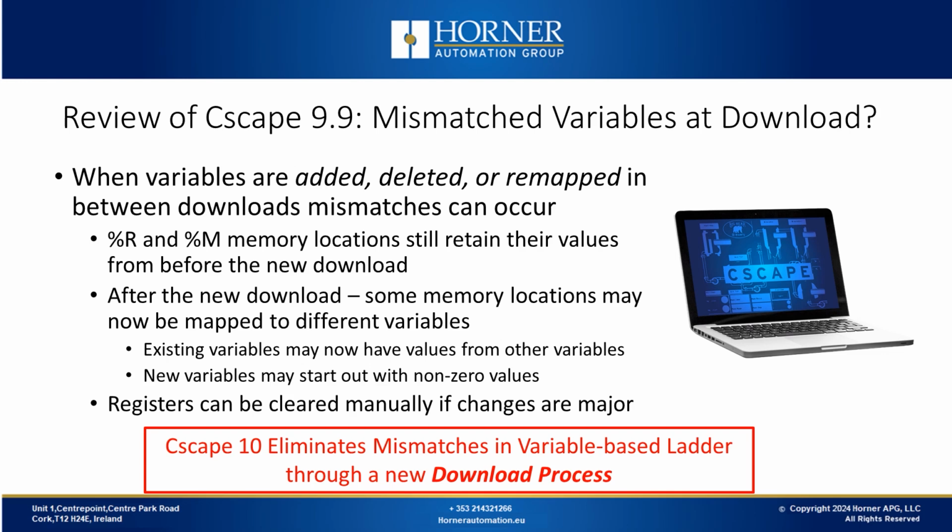So variables created just before a new download could be mapped to register locations that already contain non-zero data, and existing variables may now be mapped to new register locations that do not contain the value of that variable prior to its download. This remapping needs to be managed by system designers to avoid these mismatches.